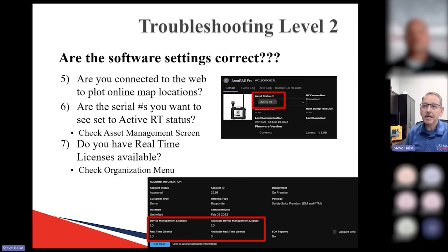That's step 6. Active RT stands for real time. I don't see any of the CST teams having an issue with this because you have so many licenses that you're sharing as National Guard Bureau altogether. But if you are trying to be thorough with your troubleshooting, you do want to make sure that each AreaRAE is set to active RT status. You have plenty of licenses to use, but if they're not set to active RT, you will not see that instrument on the software. So just make sure that under the asset management page, each AreaRAE has active RT as one of the statuses that could be set for that instrument.